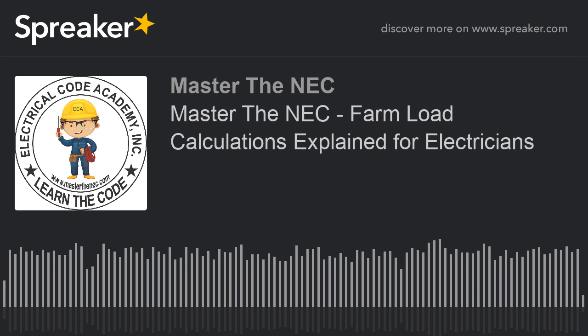Folks, first thing we want to do is ask what was the largest load? That was the simultaneous load, if you remember. That was the largest load. So if you look at this table, it says what is the largest load? Well, the largest load, you take at 100%, and that obviously was that 65 amps. That was the largest before when we did the 220.102b, and it's still the largest right now. So that's what we have. The 65 amps at full value, you write down 65 amps because it's taking that at 100%.